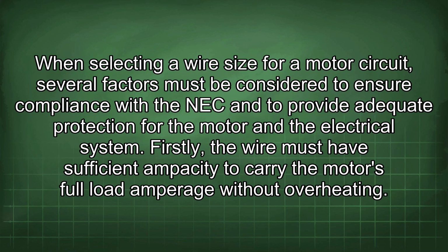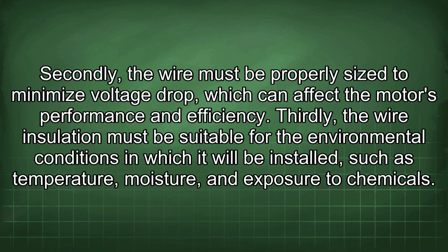motor. When selecting a wire size for a motor circuit, several factors must be considered to ensure compliance with the NEC and to provide adequate protection for the motor and the electrical system. Firstly, the wire must have sufficient ampacity to carry the motor's full load amperage without overheating. Secondly, the wire must be properly sized to minimize voltage drop, which can affect the motor's performance and efficiency. Thirdly, the wire insulation must be suitable for the environmental conditions in which it will be installed, such as temperature, moisture, and exposure to chemicals.